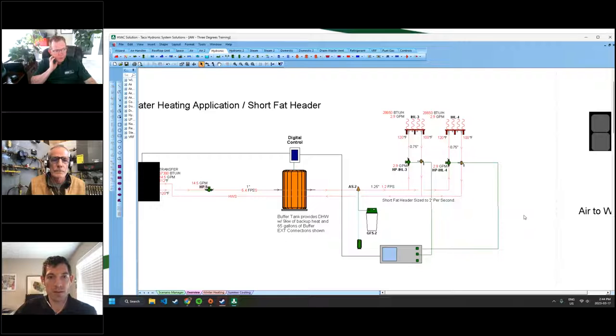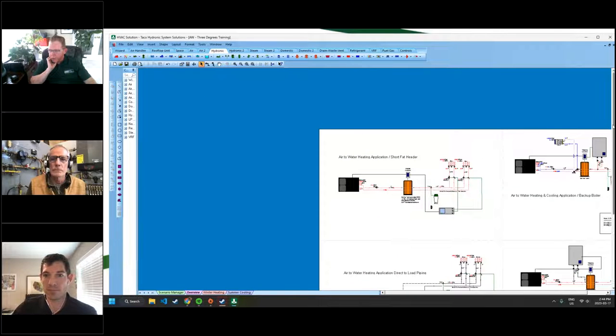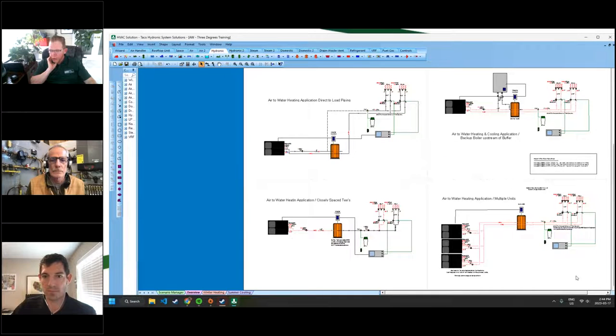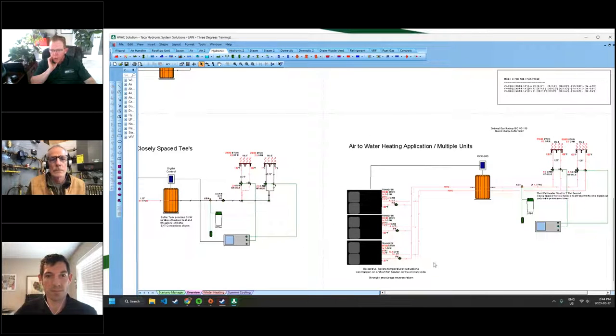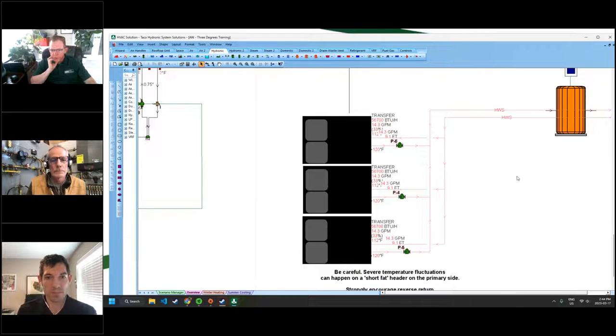So the last drawing that we wanted to sort of touch on here, and I'm just going to scroll down, is just more of a buyer beware. And where I want to focus is on this side of the system. So what I've done is I've taken three heat pumps and I put them together, and I've intentionally left the flow velocities off so we can have a conversation about it. But the idea here being that this is going to be a short fat header. So this is sized for under 2 feet per second so that these three units can't see each other. So you have to be very careful in doing this.